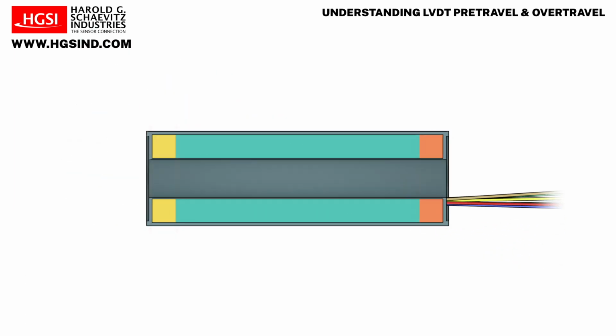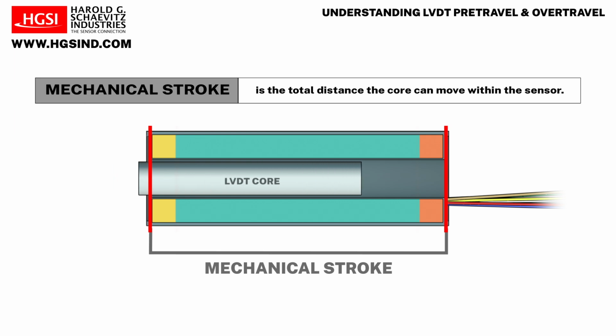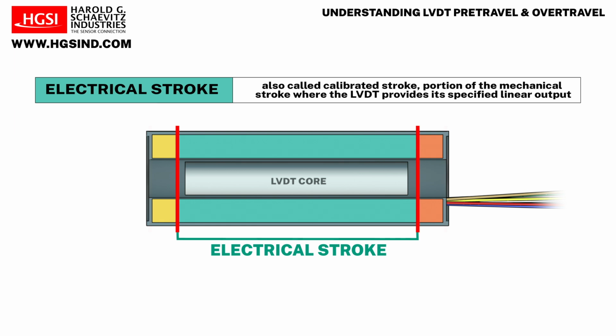Mechanical stroke is the total distance the core can move within the sensor. Electrical stroke, also called calibrated stroke, is the portion of the mechanical stroke where the LVDT provides its specified linear output. Only this range should be used for measurement.